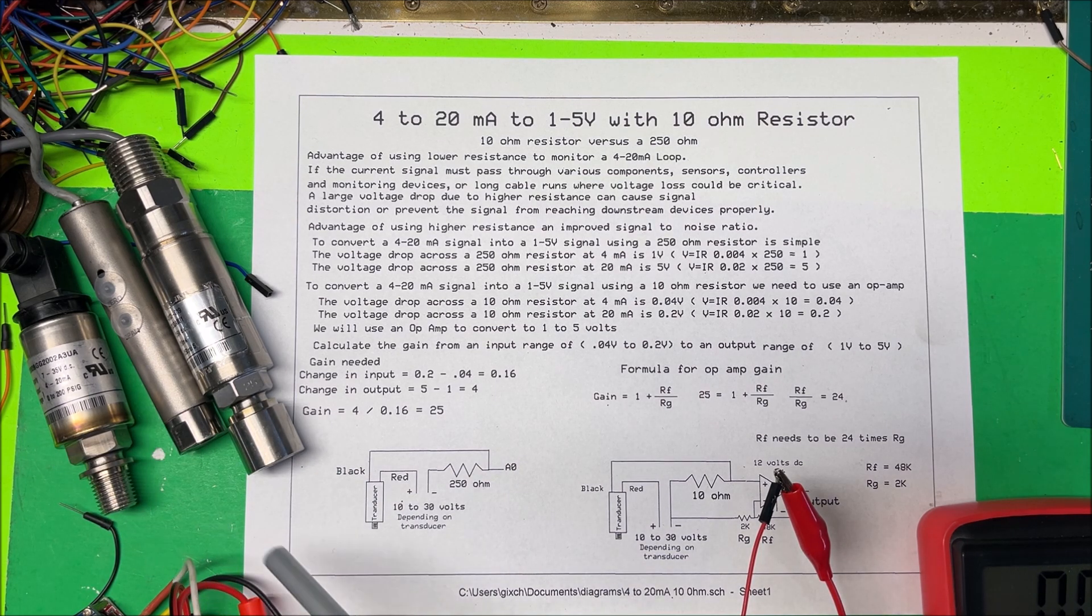But we're going to do it with a 10 ohm resistor. The advantage of using a 10 ohm resistor is that if the current must pass through a bunch of different components, sensors, controllers and monitoring devices, or you have a long cable run, then a large voltage drop due to higher resistance can cause signal distortion or prevent the signal from reaching its downstream device properly.